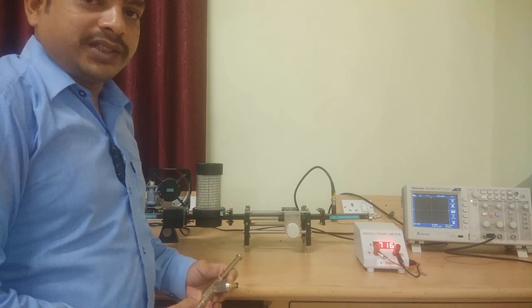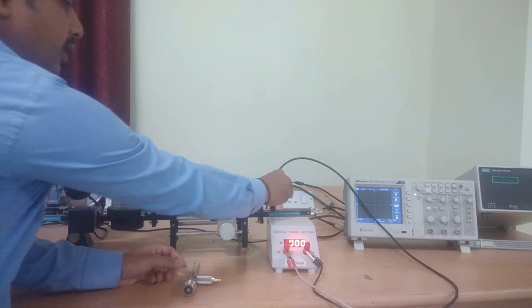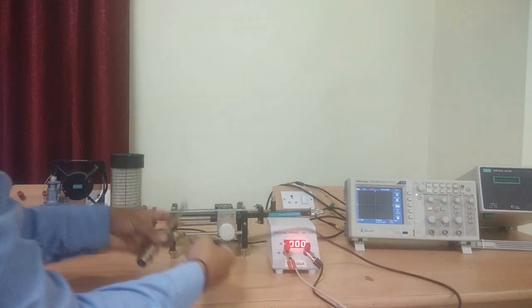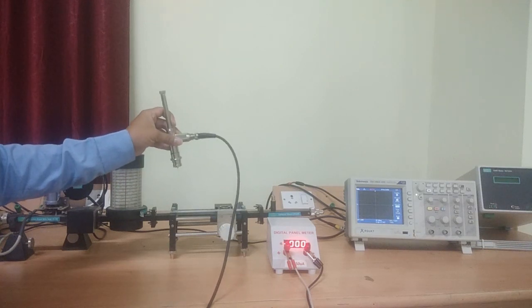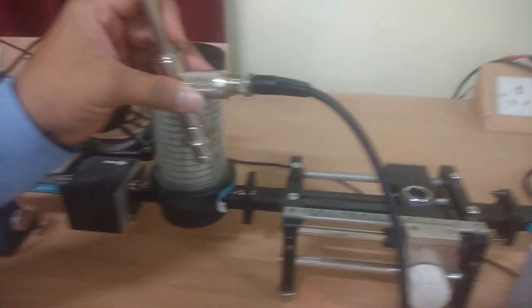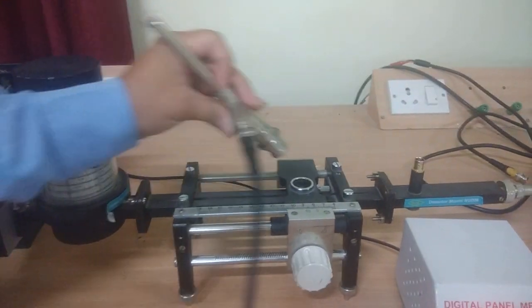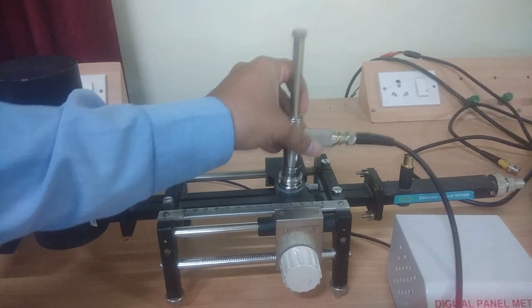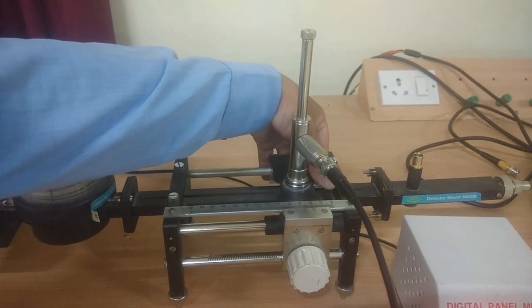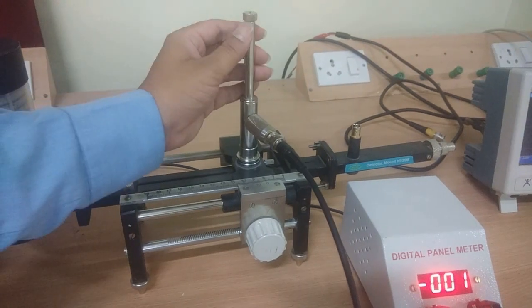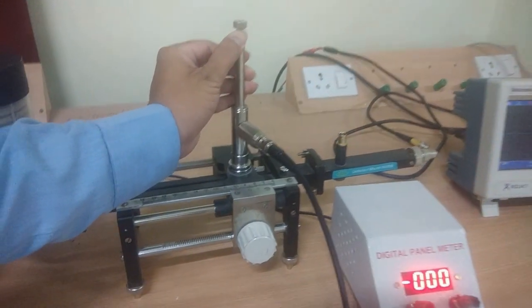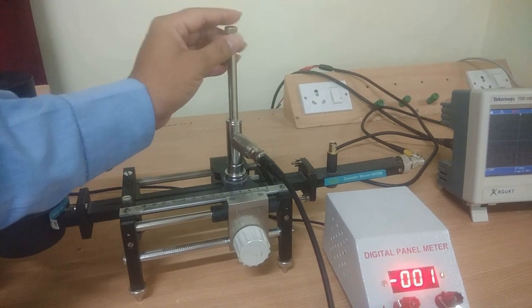The output probe is connected to crystal detector and inserted on slotted line. Here we can observe a hole to insert the crystal detector. After inserting, we have to tighten this screw. If you are getting low results, then we have to adjust this plunger to maximize our readings.